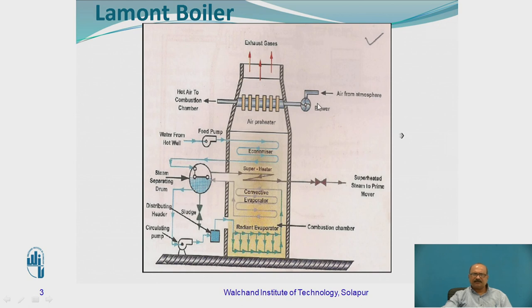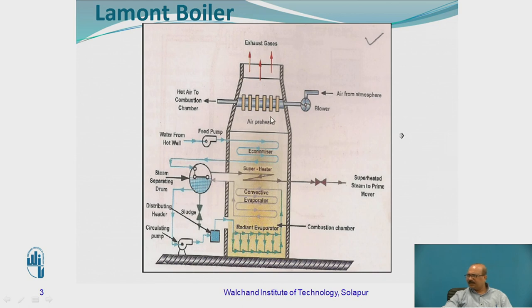I will discuss in the initial stage how exactly the working is going to take place. The blower is given on the right side of the figure. Air is going to be sucked from the atmosphere, then it comes to this blower and passes through this particular pipeline. This is the last stage of the boiler — the final part of the heat energy we are going to be extracting, which would otherwise go to the atmosphere as waste. That energy is going to be utilized, which is why we call this the air preheater. Before utilizing the air — because air is required in huge quantity — if we pass normal air from the atmosphere directly to the combustion chamber, the burning portion, it is going to cool the fuel. To avoid that, we are going to heat the air before sending it to the burning portion.